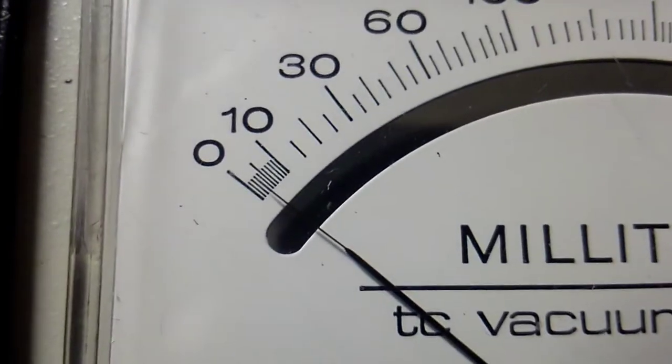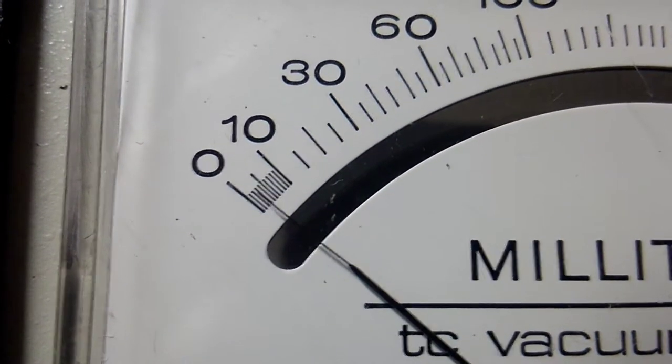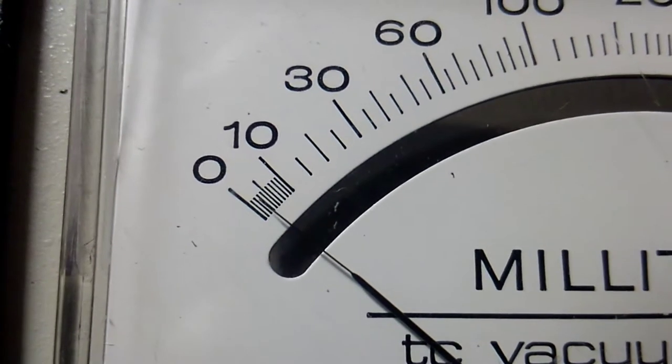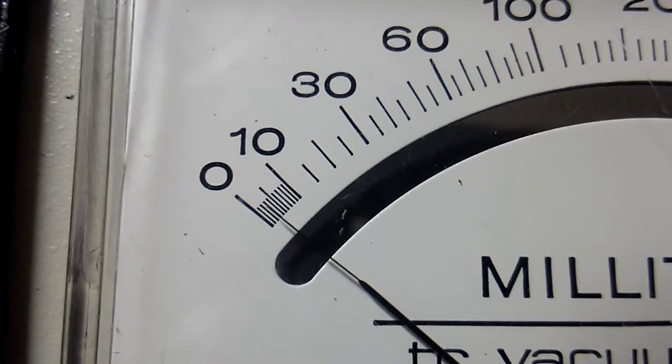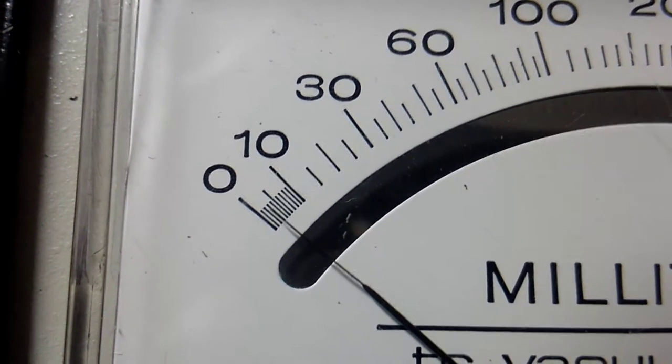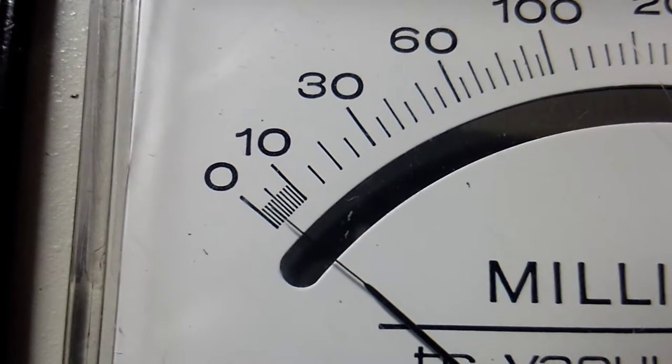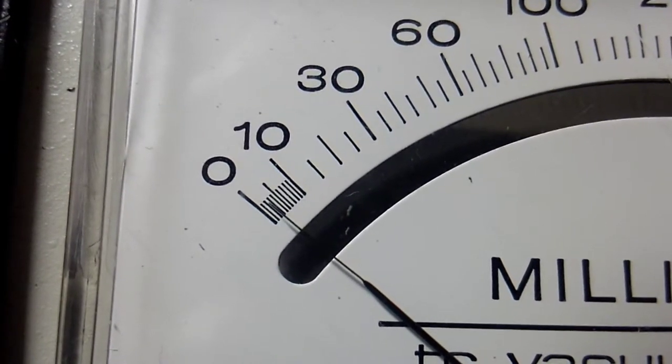The camera doesn't focus all that well. Anyway, it looks like it's about two and a half or three millitorr and it's going to be gradually coming down. If I leave it on for an hour it'll end up sitting right at the zero.